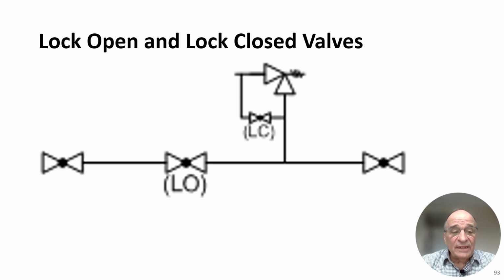Now, we should have one here as well, unless we put in an administrative procedure that forces this valve to be always in the open position. So this is a lock open valve, and this valve would be a lock closed valve. So administrative mechanisms can be used to avoid having to put an excessive number of relief valves on a plant, such as making this a lock open valve. A lock open valve is treated as a straight piece of pipe. Thus, this section of pipe is being protected by this thermal expansion valve.